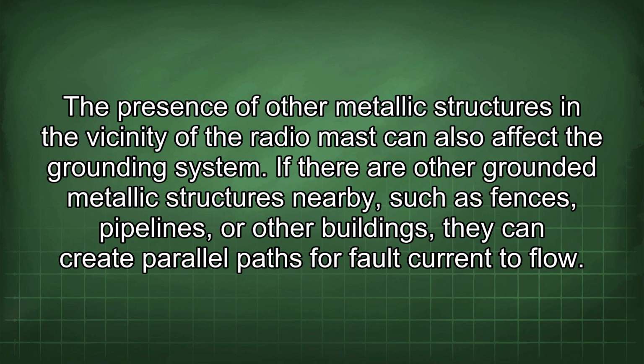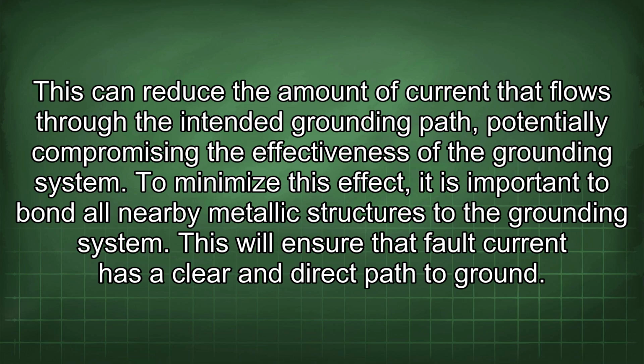The presence of other metallic structures in the vicinity of the radio mast can also affect the grounding system. If there are other grounded metallic structures nearby, such as fences, pipelines, or other buildings, they can create parallel paths for fault current to flow. This can reduce the amount of current that flows through the intended grounding path, potentially compromising the effectiveness of the grounding system. To minimize this effect, it is important to bond all nearby metallic structures to the grounding system. This will ensure that fault current has a clear and direct path to ground.